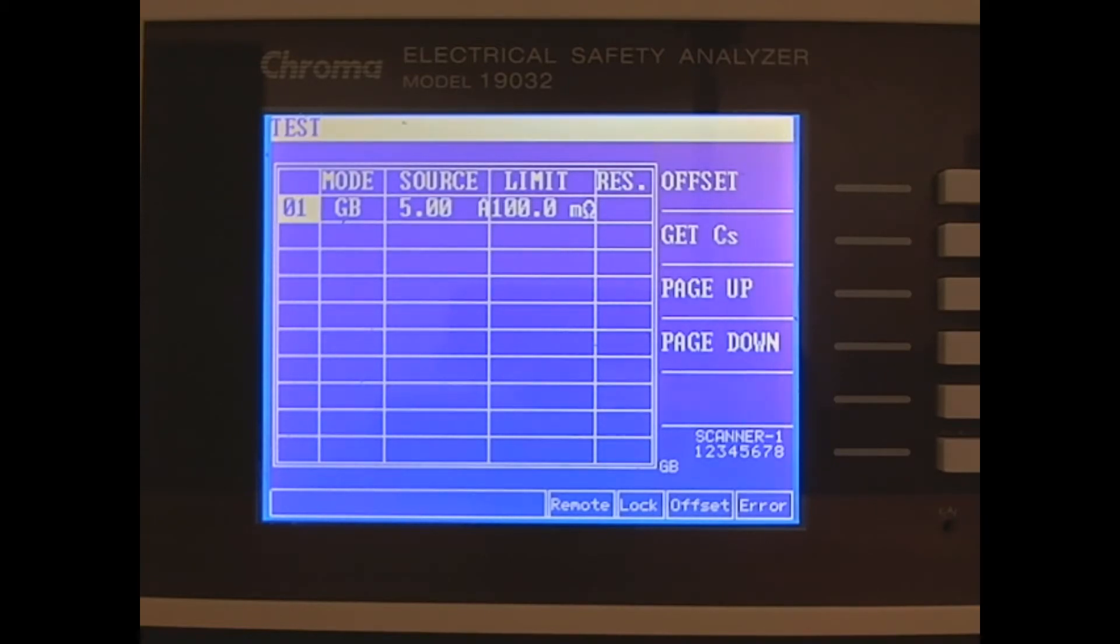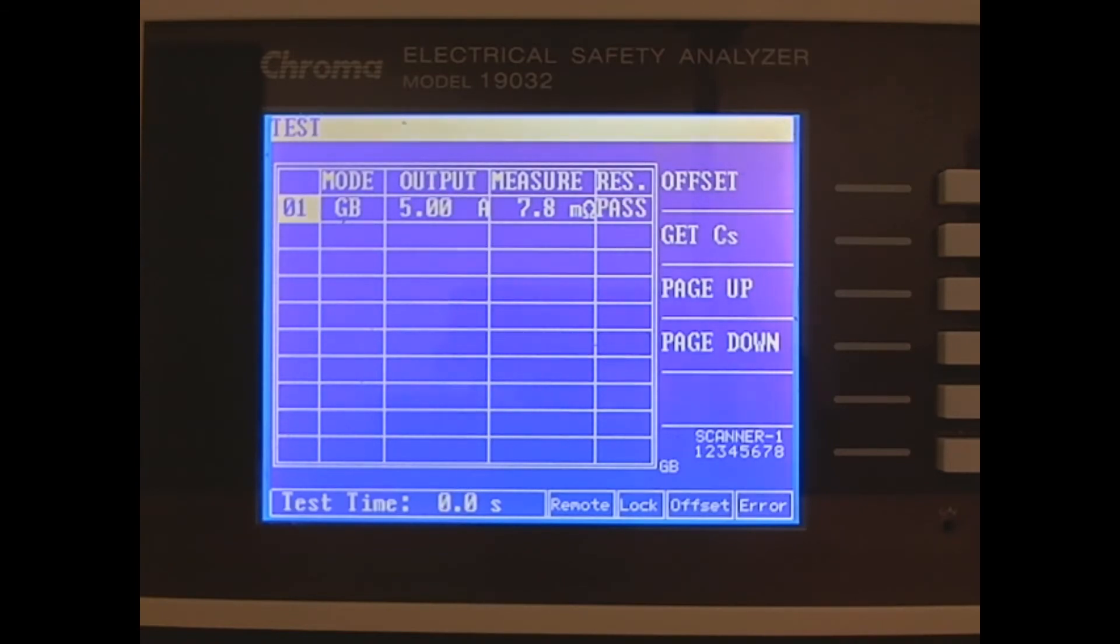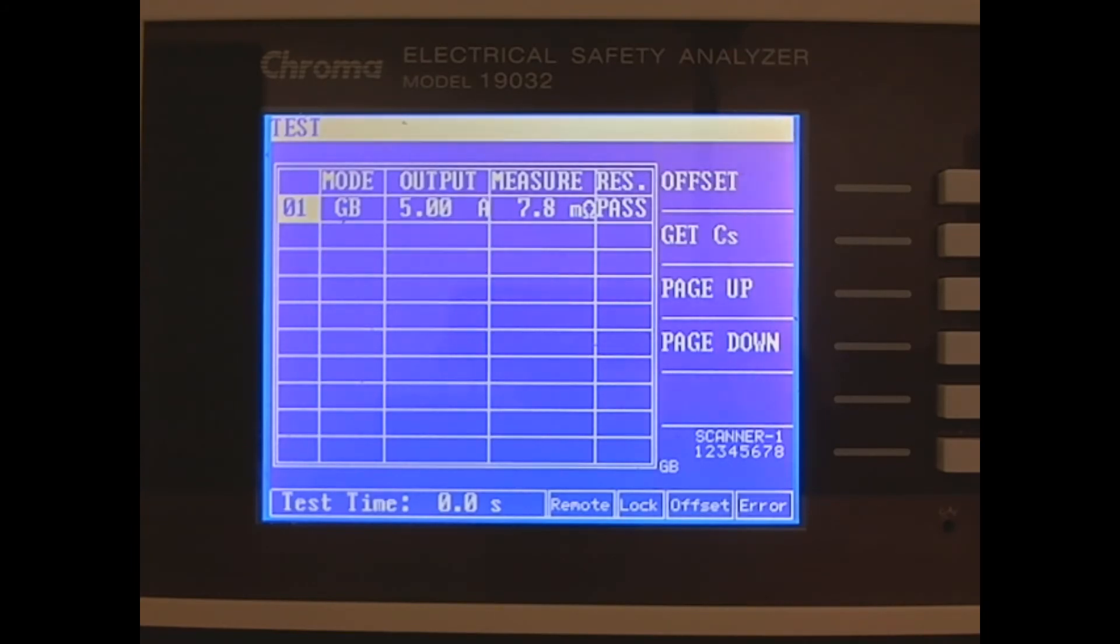And now we'll run the test. The unit detected 7.8 milliohms of resistance between the ground pin and the chassis. This is between our high and low limits, so it responds with a pass.